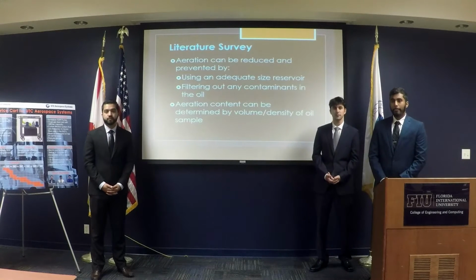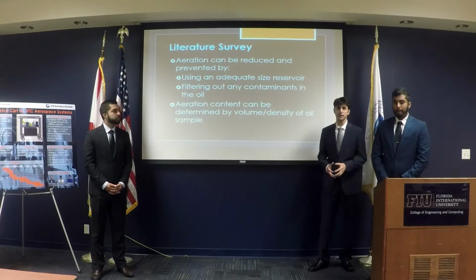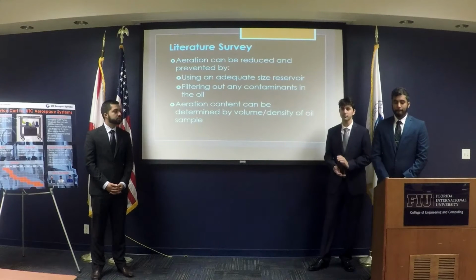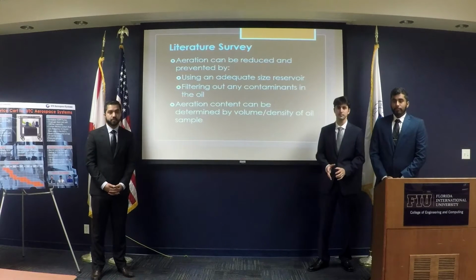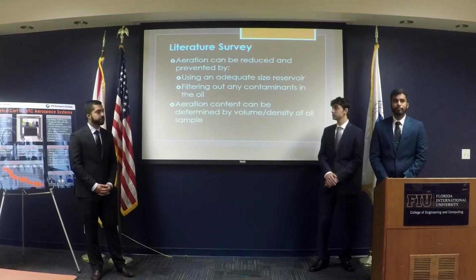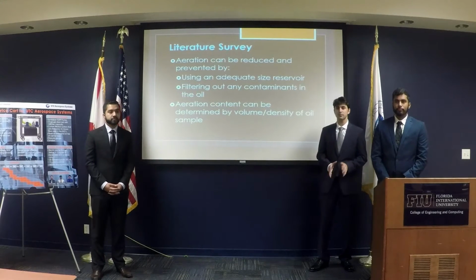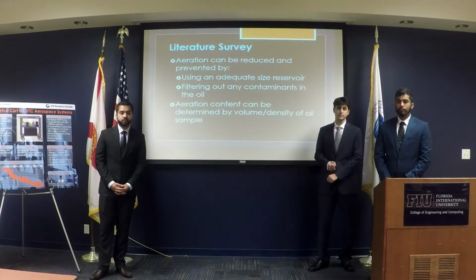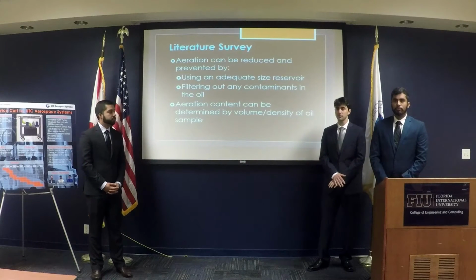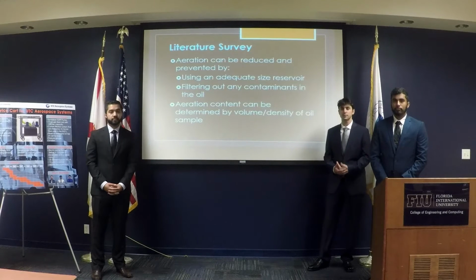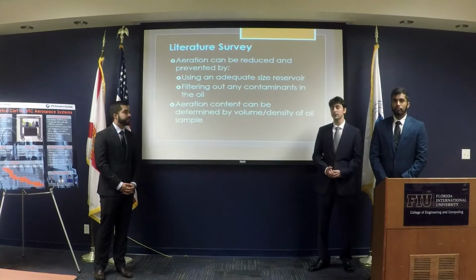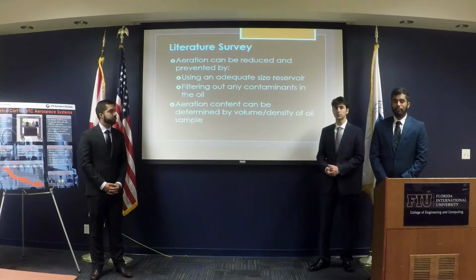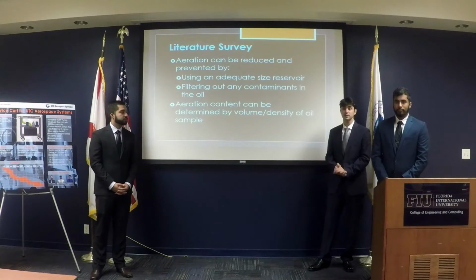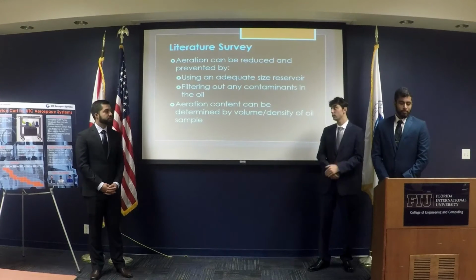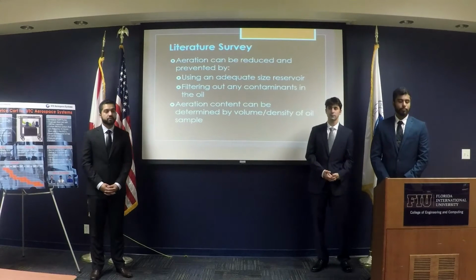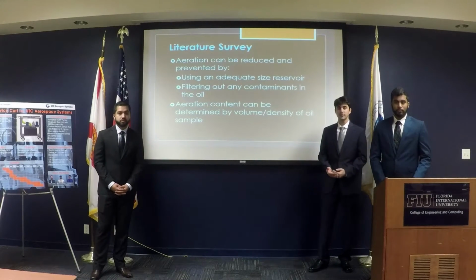The three methods we are going to focus mainly on start with reducing the size of the pump from the current test stand, which is very powerful and adds a lot of turbulence to the oil, so reducing the pump should help mitigate that. Second is using an adequately sized reservoir. If a reservoir is too small, the suction from the pump is going to cause a lot of turbulence in a small tank. Third is making sure there's no dirt in the system, so we will include a filter which will remove any contaminants, because air bubbles tend to form around the particles in the oil. And finally, our test is going to revolve around density and volume to measure the aeration content of a sample.